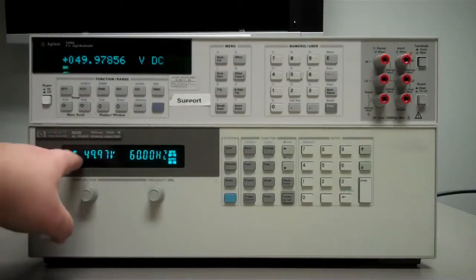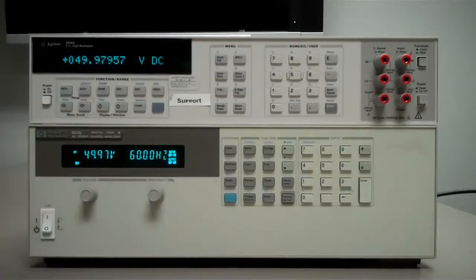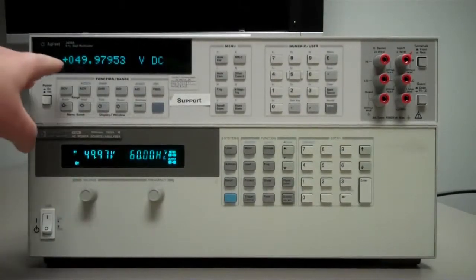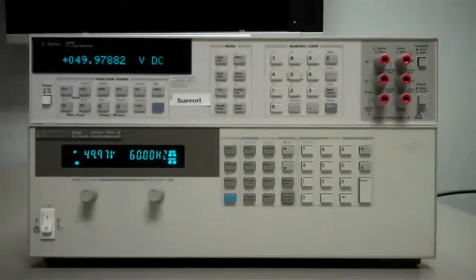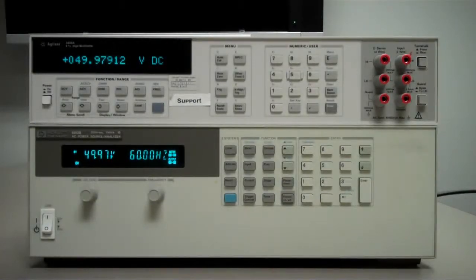Finally to enable the output, we're going to hit this output on-off key here. You can see the output is on and the AC source is measuring 50 volts. If you look up to the 3458A, that's also measuring right around 50 volts. It's a bit less, but it's within the programming accuracy specification of the DC voltage on this power supply.